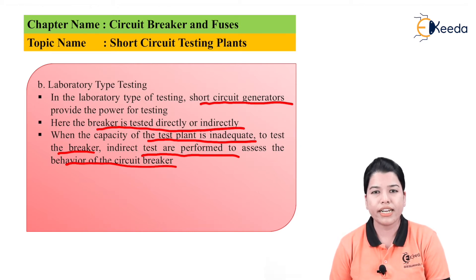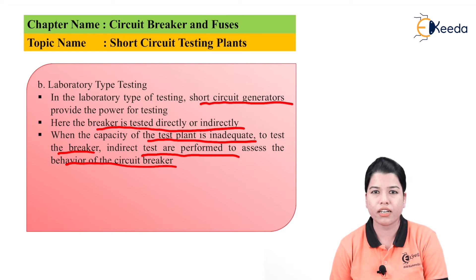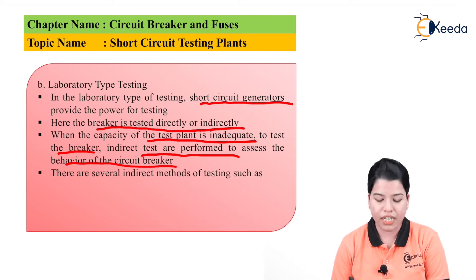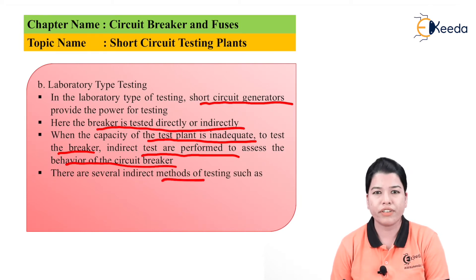In the direct test, the short circuit generator is directly connected to the circuit breaker to create short circuit conditions. If the voltage of the short circuit generator is not sufficient, then indirect testing can be done. There are several indirect methods: first is the substitution method, second is unit testing, and third is synthetic testing.